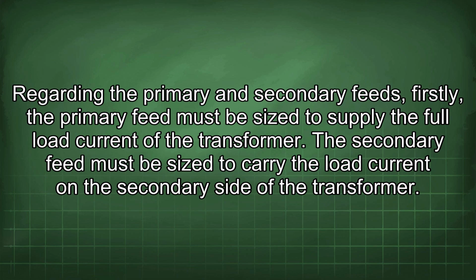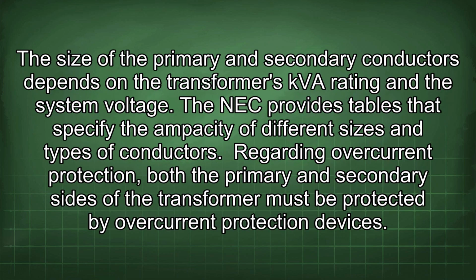Regarding the primary and secondary feeds, firstly, the primary feed must be sized to supply the full load current of the transformer. The secondary feed must be sized to carry the load current on the secondary side of the transformer. The size of the primary and secondary conductors depends on the transformer's kVA rating and the system voltage. The NEC provides tables that specify the ampacity of different sizes and types of conductors.